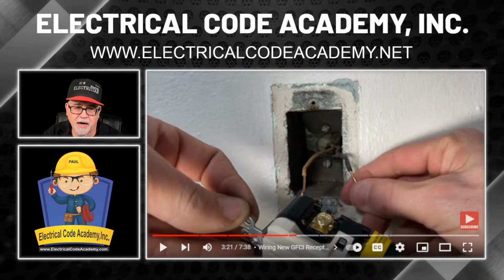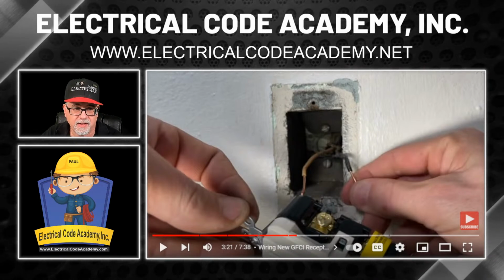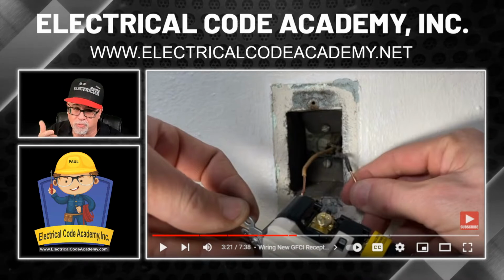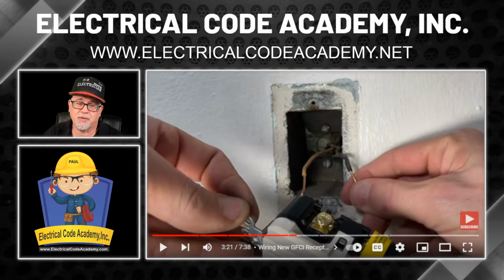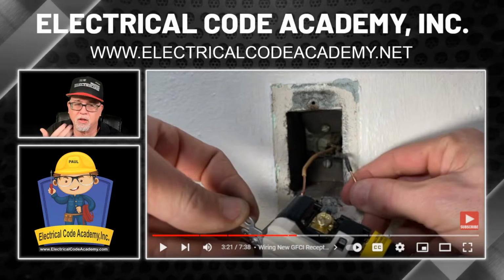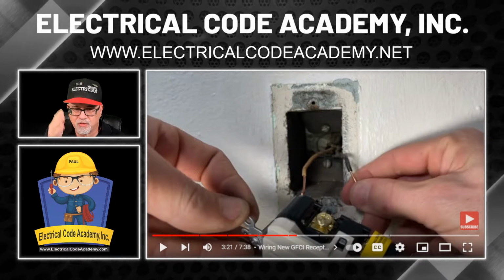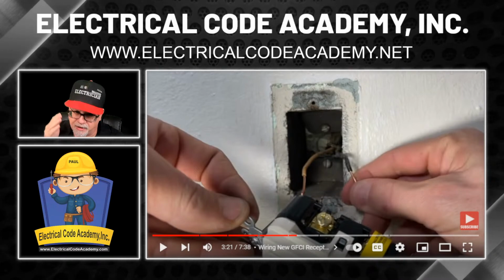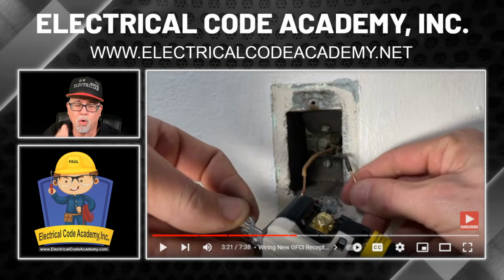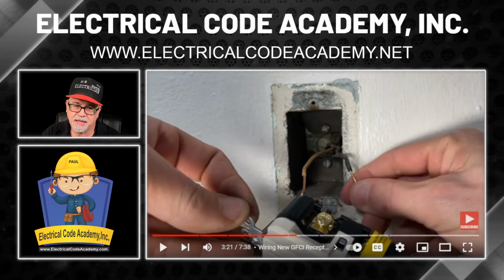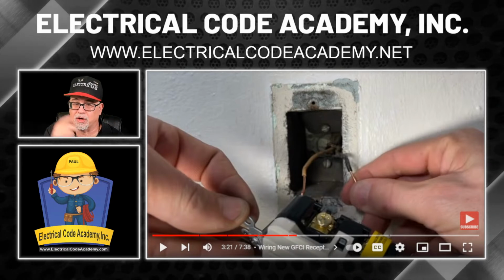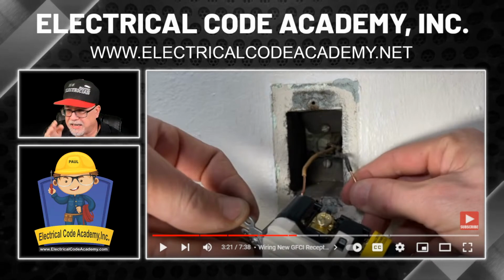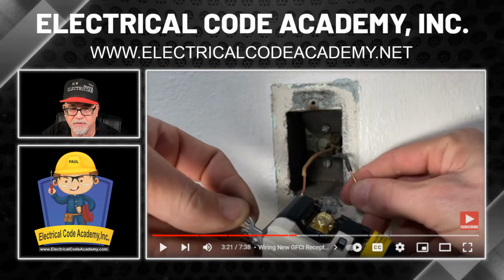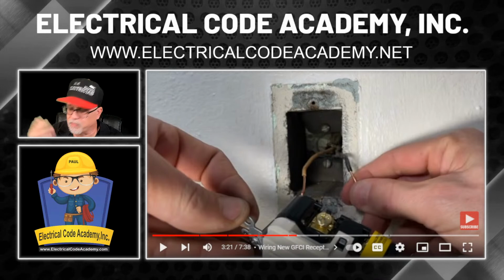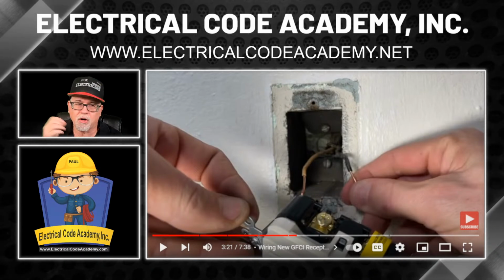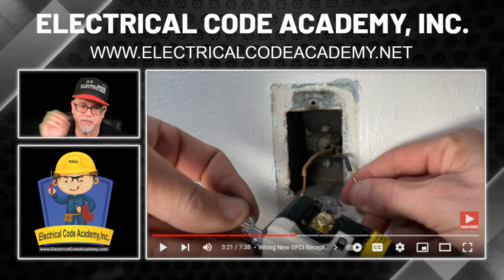In this box, he's only got 2 wires, so it's either at the end of a loop, or this was a branch circuit where only one cable was run to this location. Or maybe this is the only receptacle that he's wanting to do, and who knows what the other ones are. But again, bear in mind that since there's only 2 wires here, this is either the individual branch circuit to this location, or it's at the end of an existing branch circuit, and this is not going to do anything for the receptacles upstream. It's only going to protect this receptacle, and since he's not running any downstream, he's not using the load side of this device, then this is either the end of the line or whatnot. So just keep those things in mind. But we will talk about what to do when I have multiple receptacles in a room a little later.